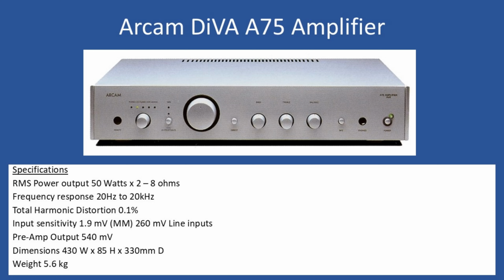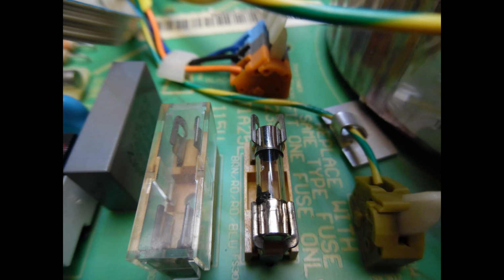When it arrived, the first thing to check is to verify if the input mains power protection fuse is intact or has failed. Here you can see the fuse has gone open circuit, which would indicate there was quite a high current consumption. The fuse is a time delay type, rated at 1.25 amps.